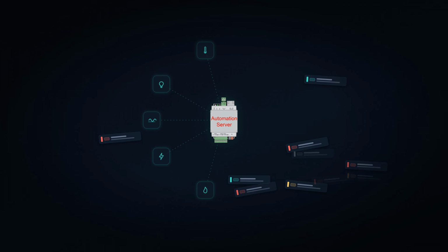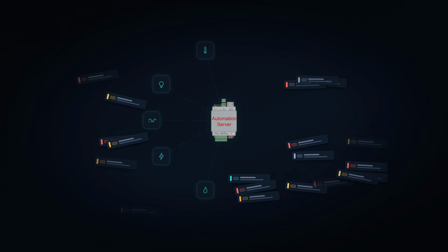The automation server runs the building and shows it live on large screens through a web-based SCADA graphic display opened in a browser. But running a building is not enough. It must also be watched continuously. Each of the building's dozens of subsystems raises its own warning: a fault, a crossed threshold, a weakening battery. When these warnings are not gathered into a single order, a critical alarm gets lost among hundreds of trivial notifications.